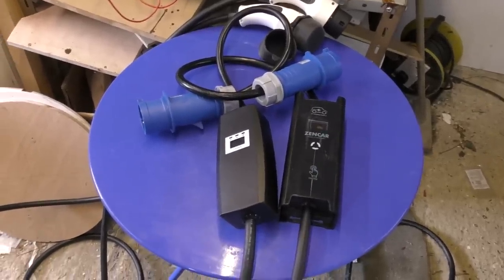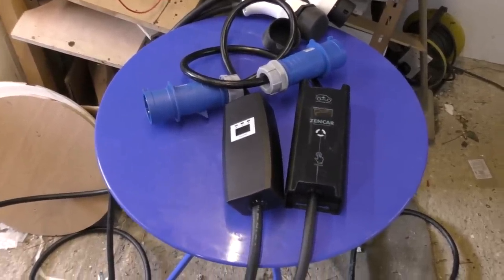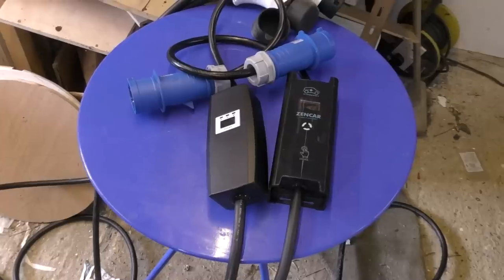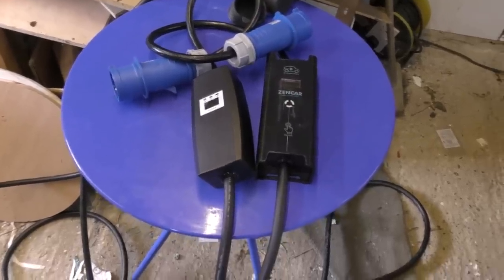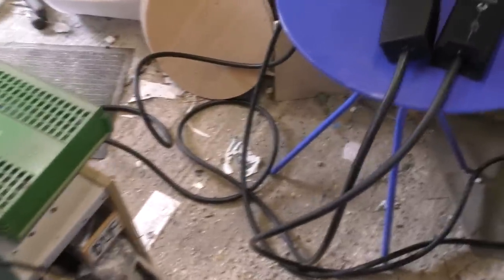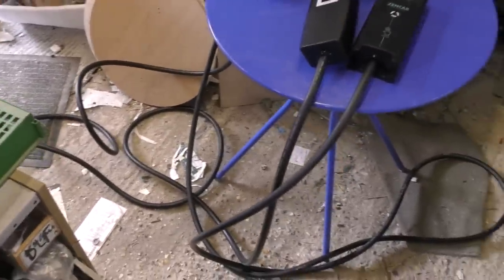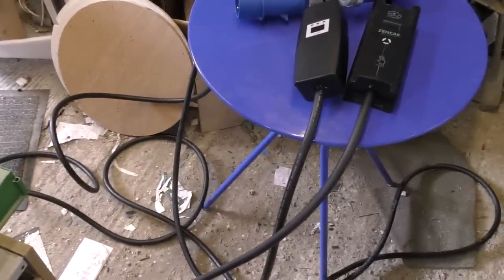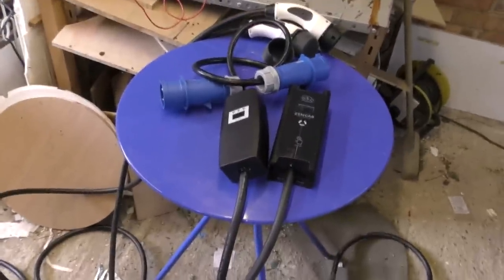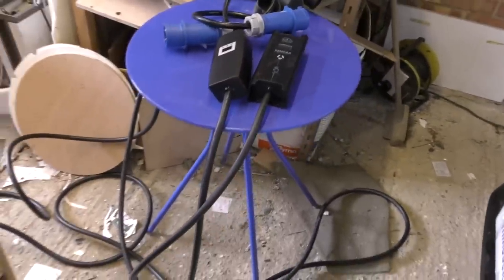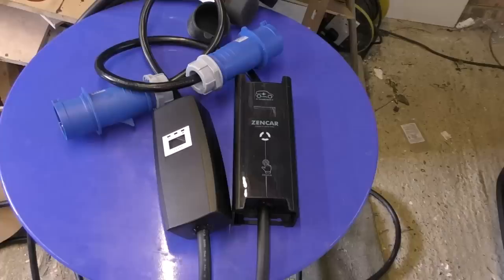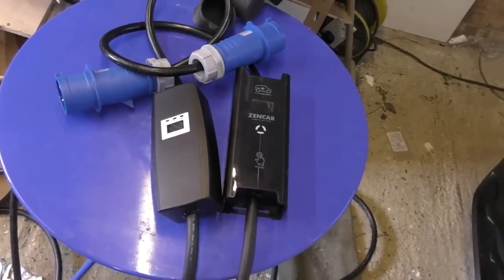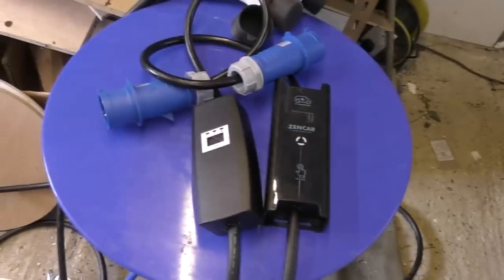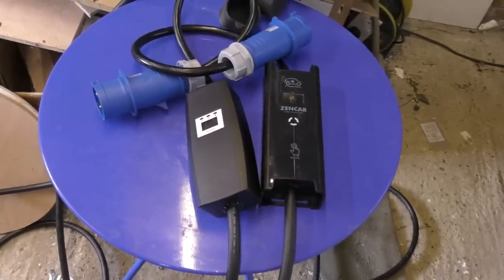So you obviously have to balance the likelihood of that happening versus potential consequences. But obviously the primary thing is AC fault detection, and in this situation, the most common likely scenario is a cable that's maybe got damaged by being run over or by repeated flexing, or water ingress into the plug. An AC RCD will generally detect that. So I'm just going to go through the functionality of these first, and then we'll take them apart and have a more detailed look and do some tests.